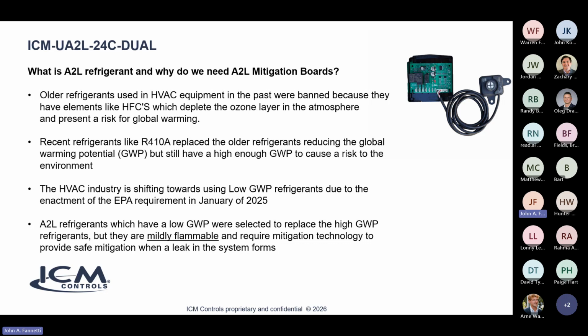So the HVAC industry now is leaning towards using only low GWP, or low global warming potential, refrigerants due to the enactment of the EPA requirement in January of 2025. So now A2L refrigerants, as they're labeled, have a low global warming potential, and they were selected to replace the higher global warming potential refrigerants like the 410A. But unfortunately, they're mildly flammable. So they require some type of mitigation technology in order to provide safe mitigation when a leak happens, okay?